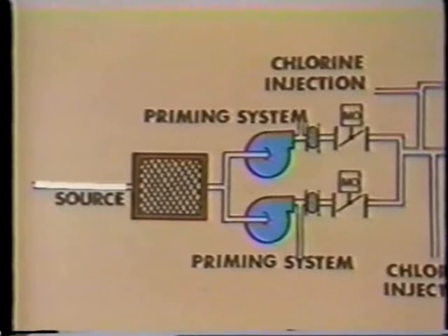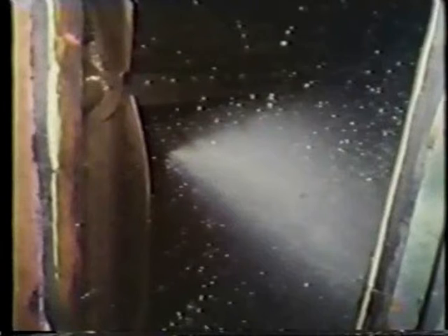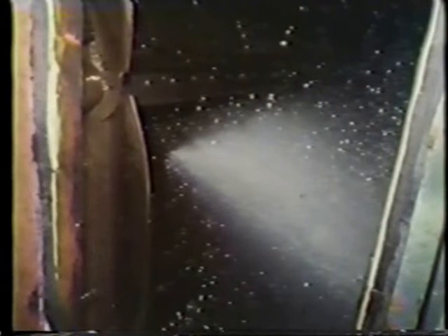Since the water source can have a lot of trash and debris, there are usually coarse screens and fine screens between the water source and the circulating water pumps to filter out this debris. Coarse screens, often referred to as trash racks, filter out large debris such as logs or branches. Fine screens filter out smaller debris such as litter or trash. Fine screens are often referred to as traveling screens because they rotate into and out of the water when necessary. When these screens are rotated out of the water, they're usually sprayed with water to clean off the debris.